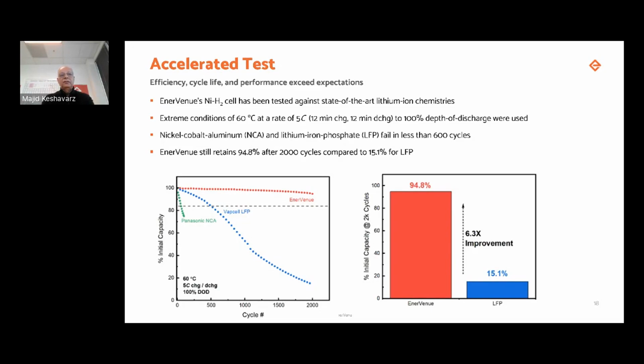We ran it for 2,000 cycles, and EnerVenue battery as well, and we see that only losing 5% of its capacity after 2,000 cycles, whereas LFP reached 15% or so. Very different behavior. This is why this type of batteries are known to be very durable and basically can handle harsh conditions, hot and cold.